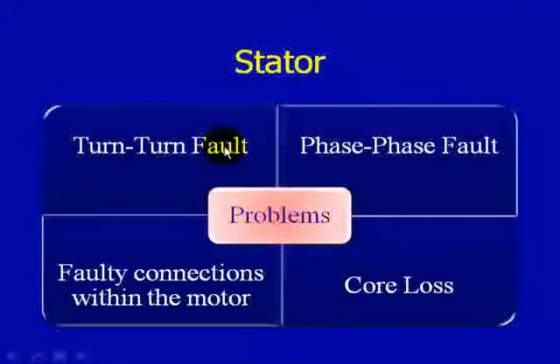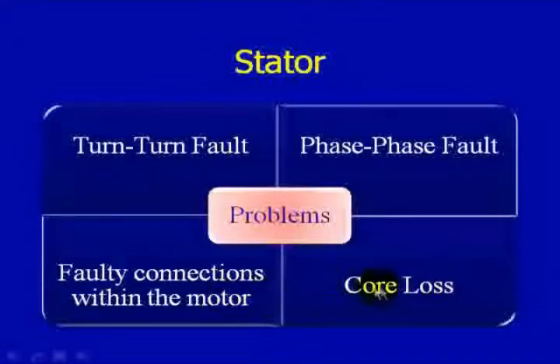Think about the rotor fault zone. If you have an anomaly in the rotor, it could be creating high heat in that rotor. That rotor is very close to the stator, and that excess heat could also potentially degrade the insulation of that stator. When we look at faulty connections within the motor, we're talking about dead solder connections or faulty solder connections inside the motor. Core loss, or loss of core lamination — essentially we're worried about excess heat as well, and that excess heat could destroy that insulation over time and cause a potential fault inside the stator.